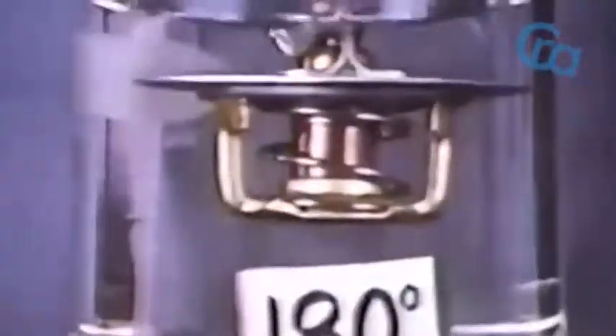During light engine load operation, the thermostat partially closes to prevent subnormal operating temperatures. This word of warning: never allow an engine to operate without its thermostat installed. Most engines have a normal operating temperature of at least 180 degrees Fahrenheit. When an engine runs below best operating temperature, fuel that hits the relatively cold combustion chamber or cylinder walls will not burn. This raw fuel dilutes the lube oil on cylinder walls and helps carry contaminants into the crankcase oil. This excess fuel also reduces the oil film thickness on the walls, which in turn allows faster wear of rings and liners and increased blow-by.